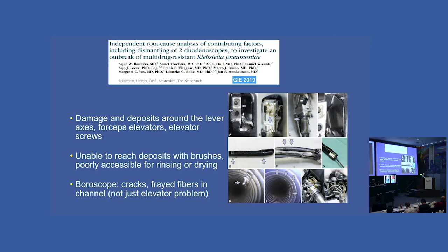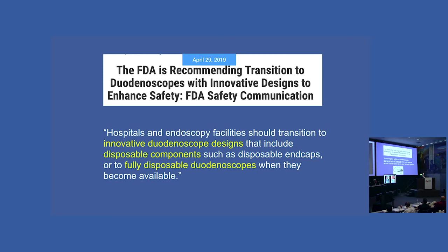So the FDA started in April of last year. They recommended a transition to duodenoscopes with innovative designs to enhance safety. So it's no longer business as usual, folks. Something has to change. The FDA is telling us something has to change. So either we're going to go to disposable components, or we're going to go to fully disposable duodenoscopes when they become available. And they became available in December.